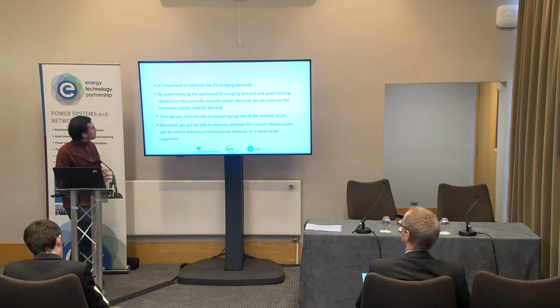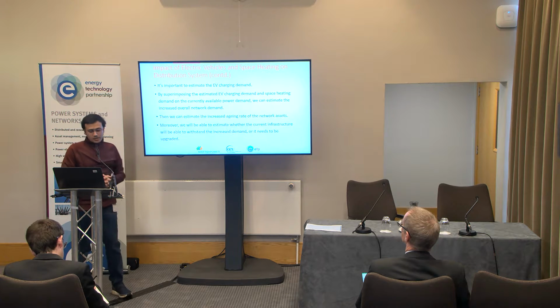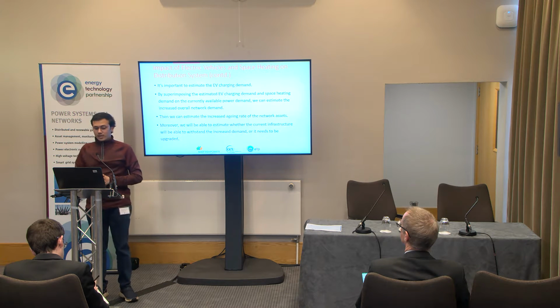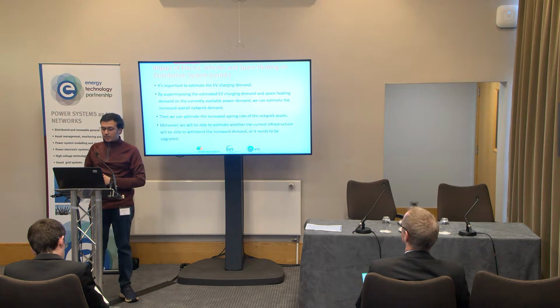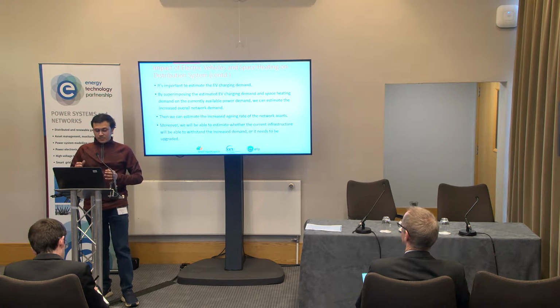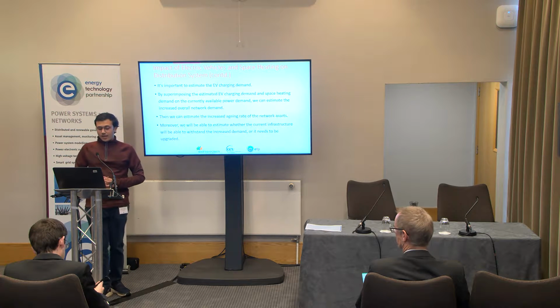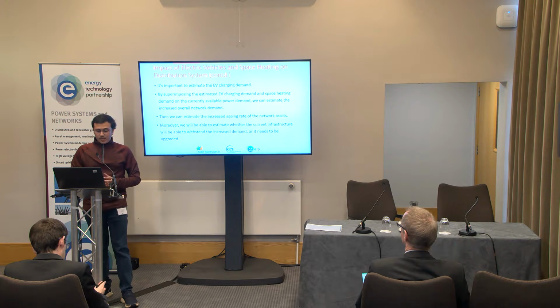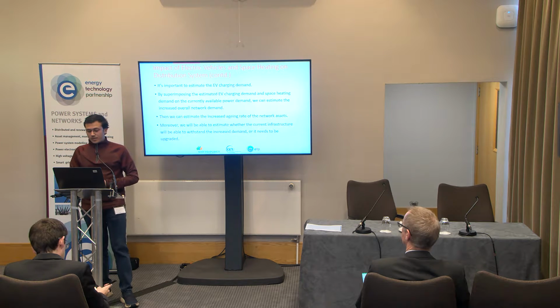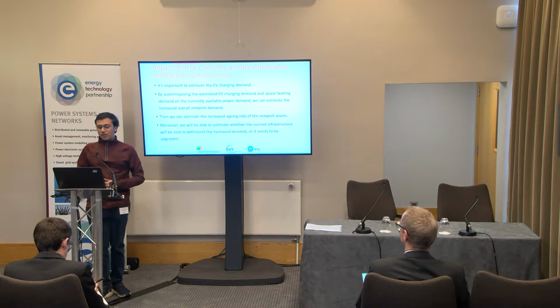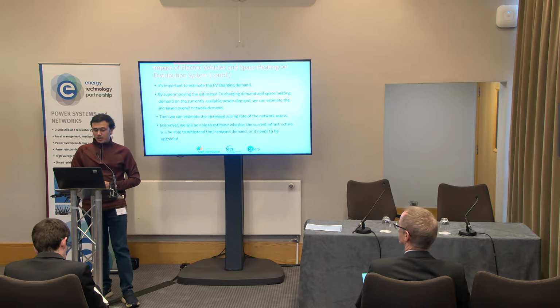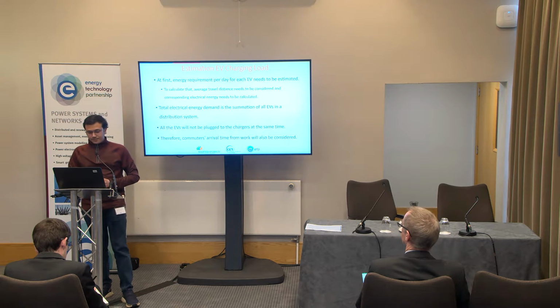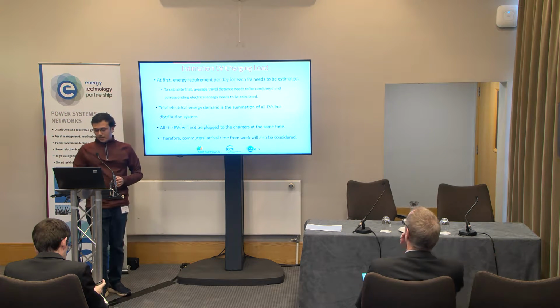So here we see that it's important to estimate the EV charging demand. By superimposing the estimated EV charging demand and space heating demand on the currently available power demand, we can estimate the increase of overall network demand. Then we can estimate the increased aging rate of a network asset, for example a transformer. Moreover, we will be able to estimate whether the current infrastructure will be able to withstand the increased demand, or whether it needs to be upgraded.